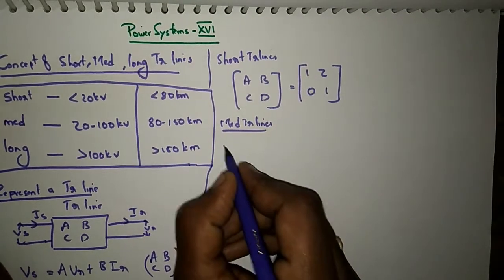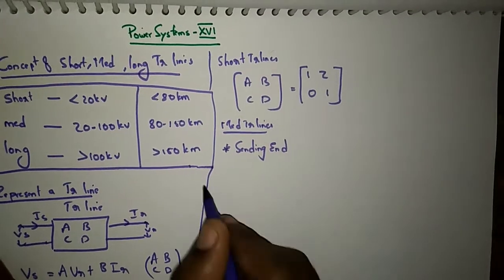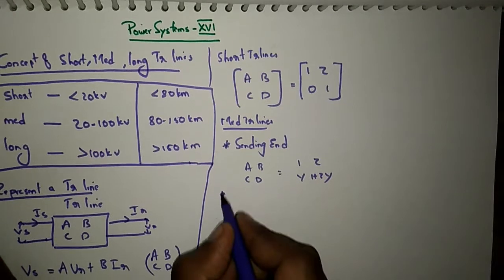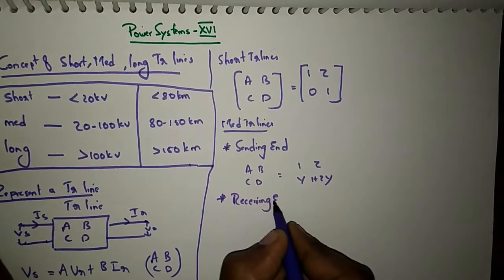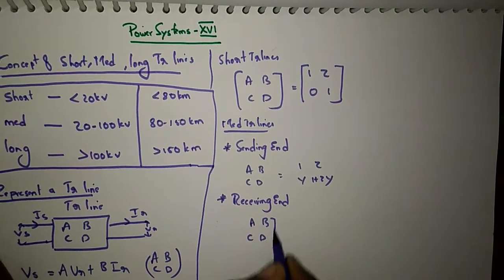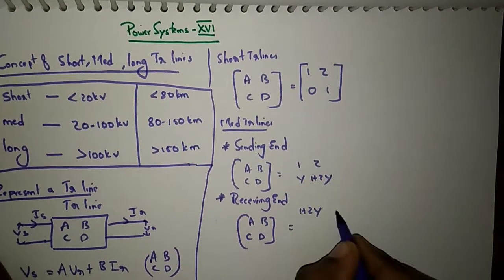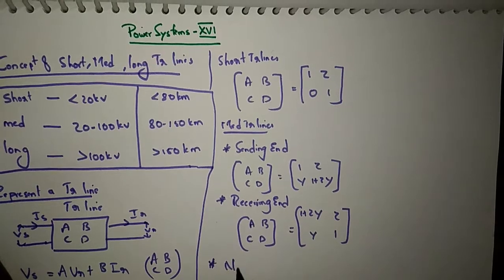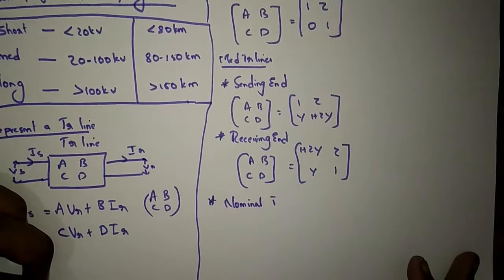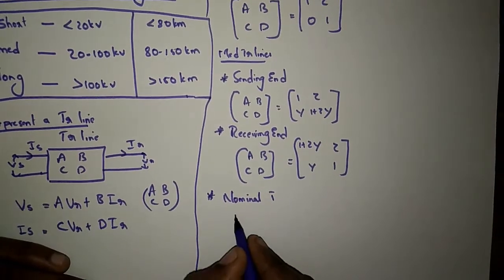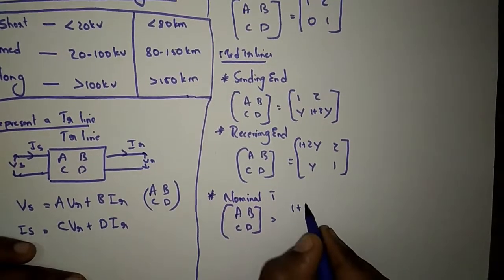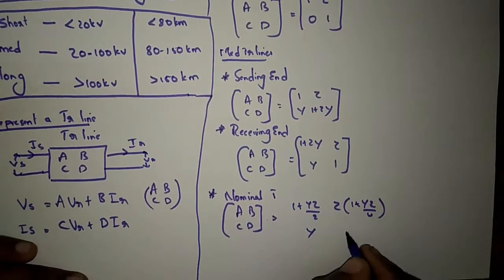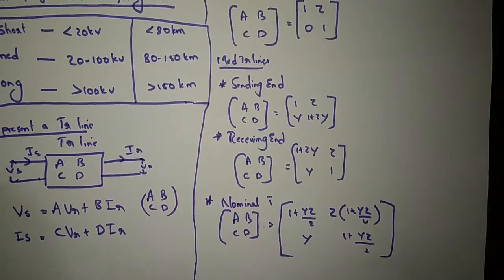For medium transmission lines there are different types. For the sending-end pi (nominal π) type, the ABCD values are: A = 1, B = Z, C = Y, D = 1 + ZY. For the receiving-end type, the ABCD values are: A = 1 + ZY, B = Z, C = Y, D = 1. For the nominal T method, the ABCD values are: A = 1 + YZ/2, B = Z(1 + YZ/4), C = Y, D = 1 + YZ/2.